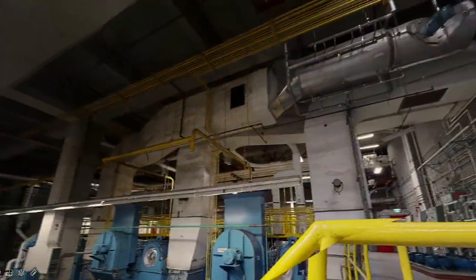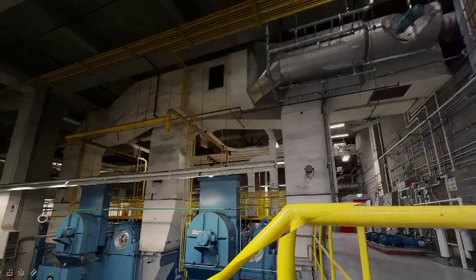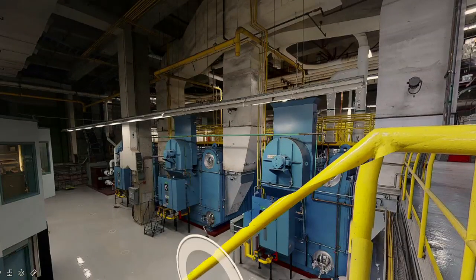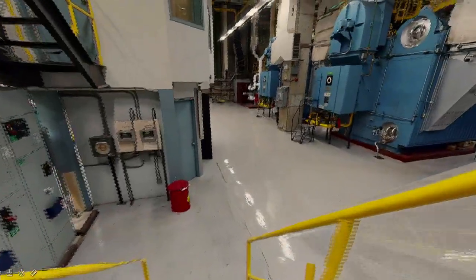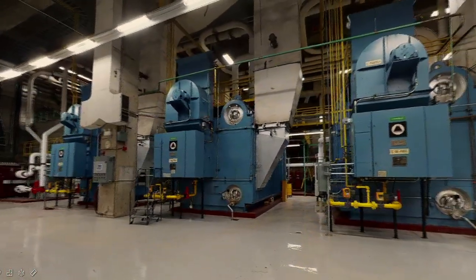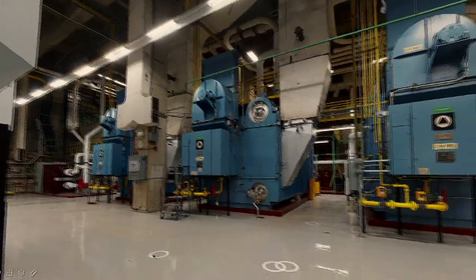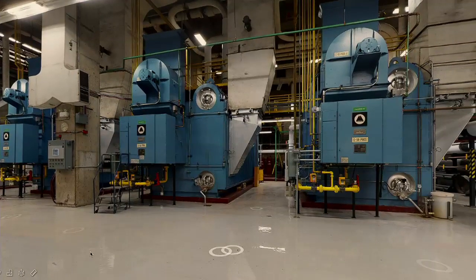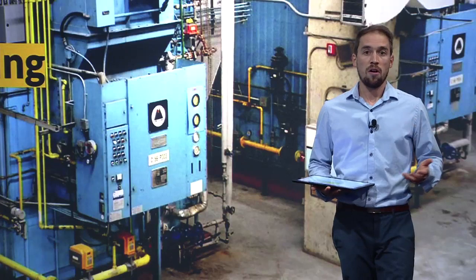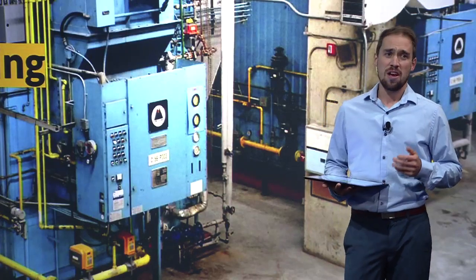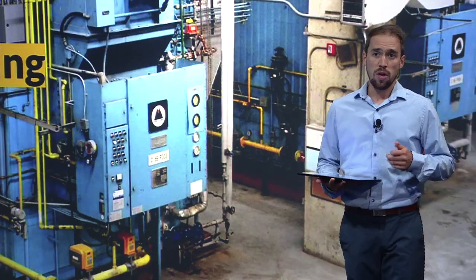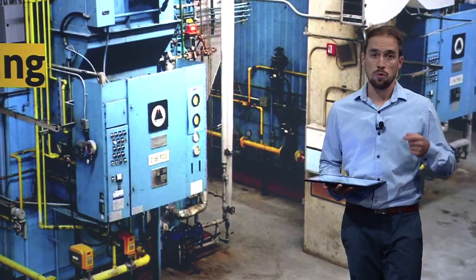Most of the time when we do a steam to hot water conversion for boilers, the regular solution is to replace them with new hot water boilers. But in this case, in order to reduce the cost of the project, we wanted to reuse them. We have to understand that at the Olympic Stadium, the boilers have to be really big, because when there's a major event in the playfield area we need a lot of capacity. But unfortunately they don't operate many hours a day at high capacity, so there's not a lot of savings related to it. So in order to reduce the cost, we wanted to reuse them.